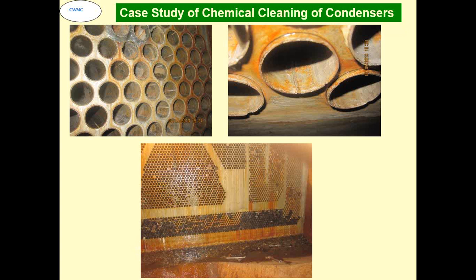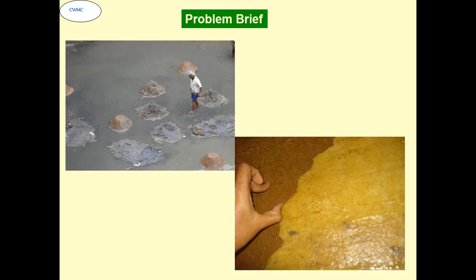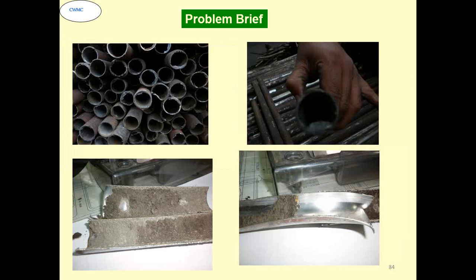These tubes are seam welded tubes, and around 4,000 tubes failed at a time. When we analyzed, that was the problem we found. This is the kind of thing you see: the fly ash mounds inside that cooling water system. These were the tubes which were choked. You can see the fly ash inside the condenser tube, and when it was cleaned, you can see in one place it was shining; at the seam weld there was corrosion.